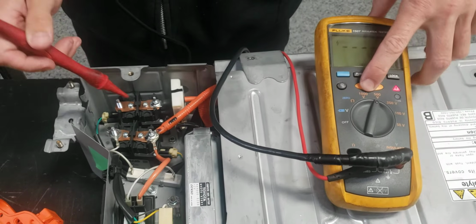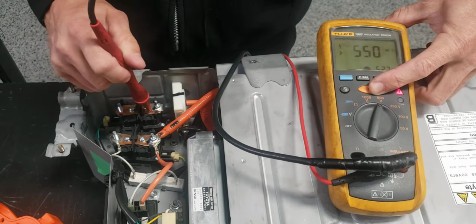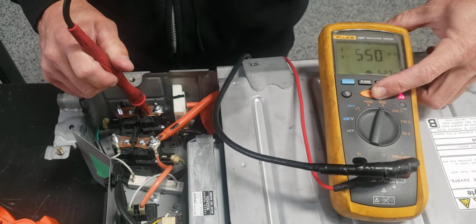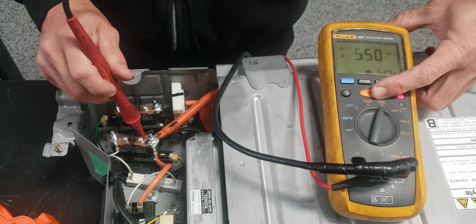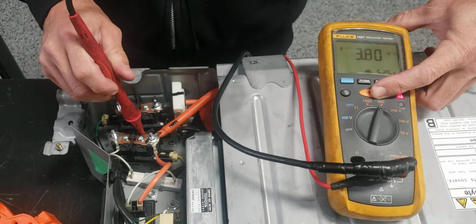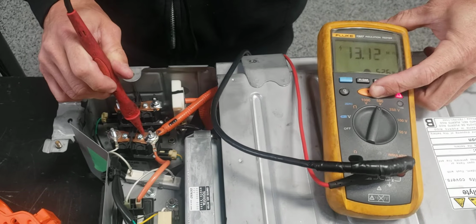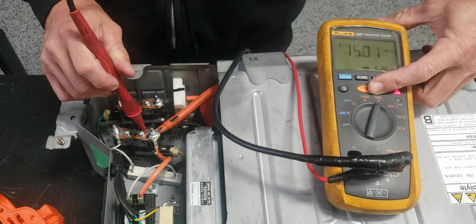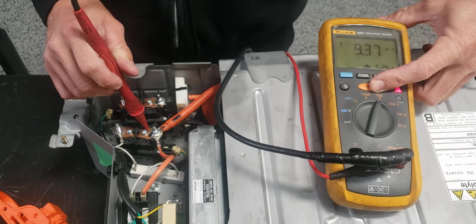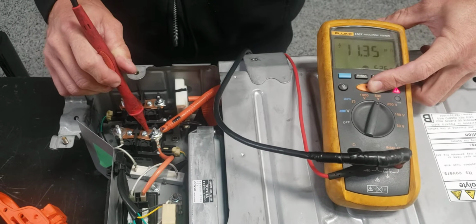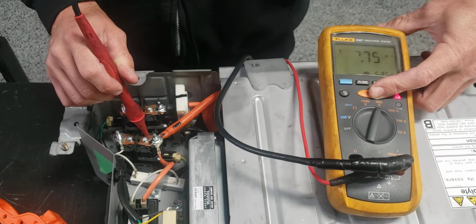So this first one, I push down, and I get a reading of 550 mega ohms - it's good. Go to this next one, and it's really low, it's bouncing around. I'll explain in a little bit why it bounces around, but the numbers should be pretty static. So we definitely have an issue.